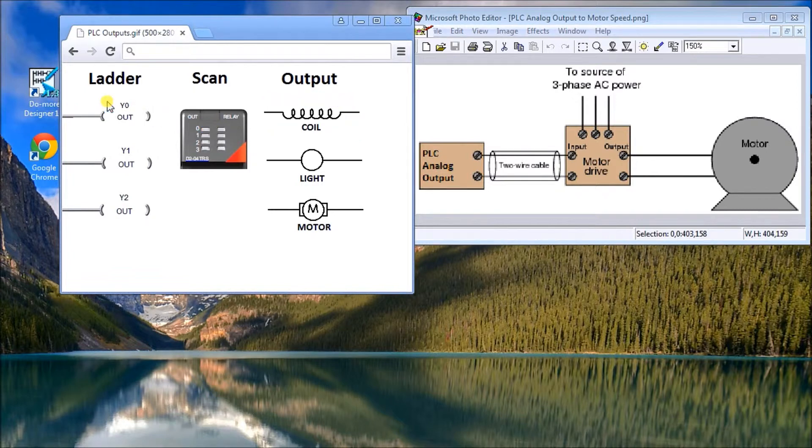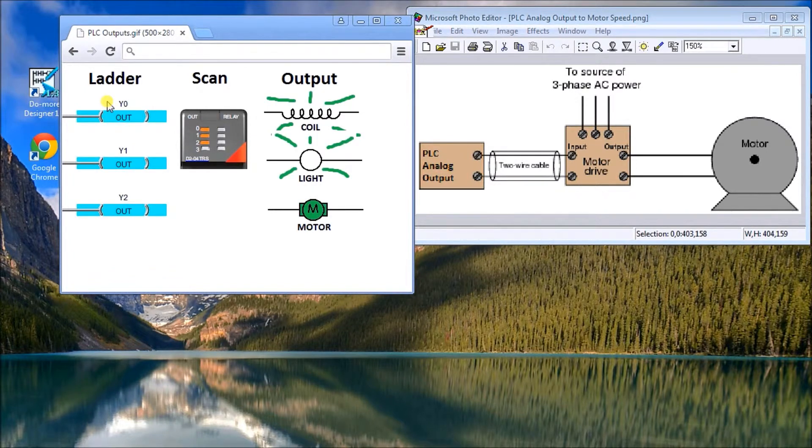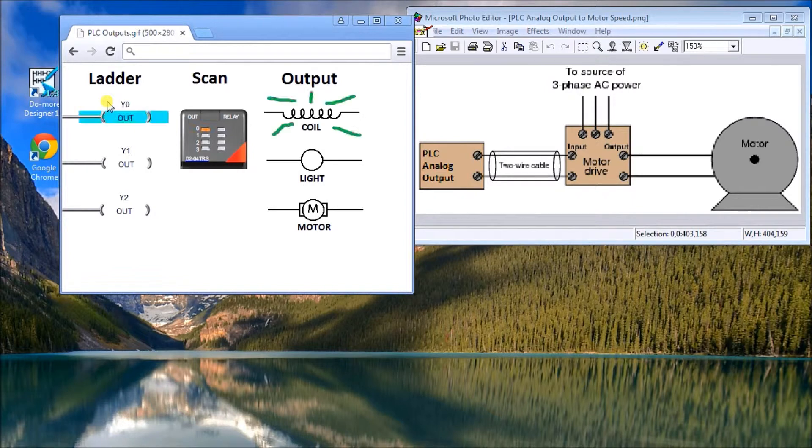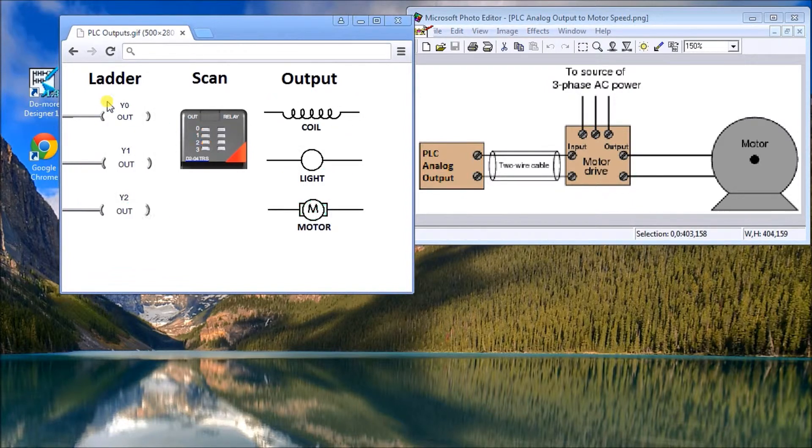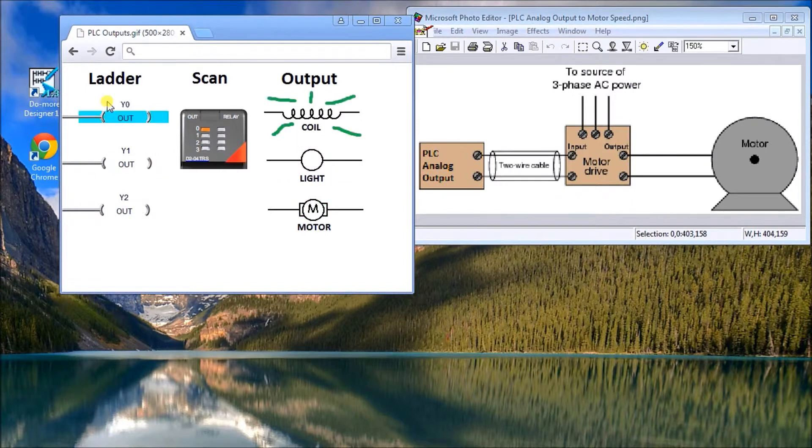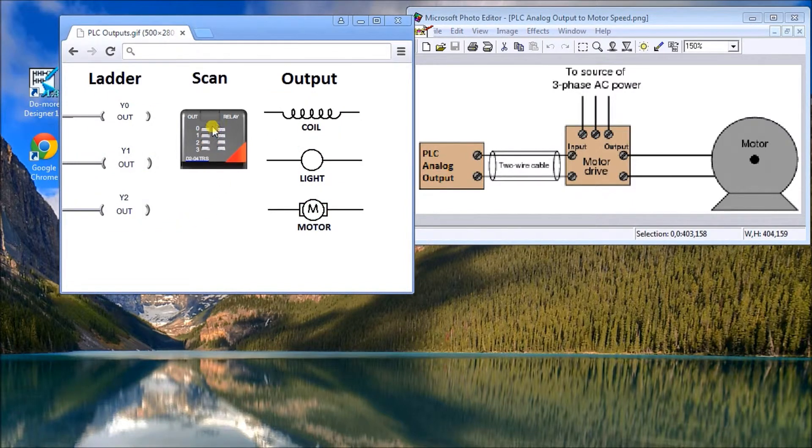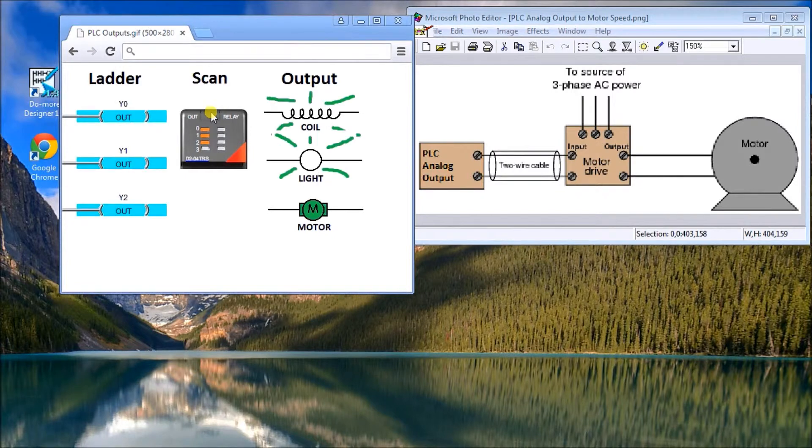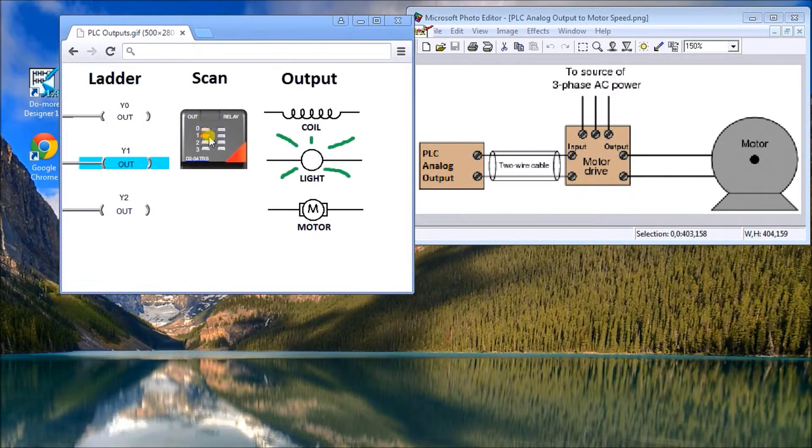My ladder is solved left to right, top to bottom in most PLCs. There are a few exceptions. At the end of every scan, the output table is then set according to what the ladder logic told us to do, and then it will actually set the physical outputs, which you'll see actually come on. That means whatever is wired to that output will be energized.